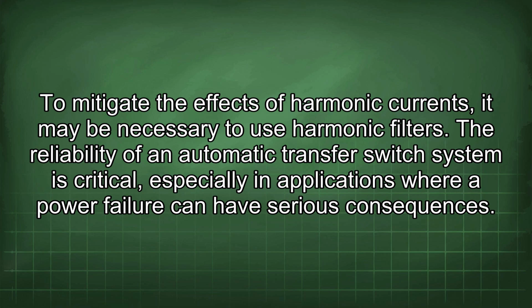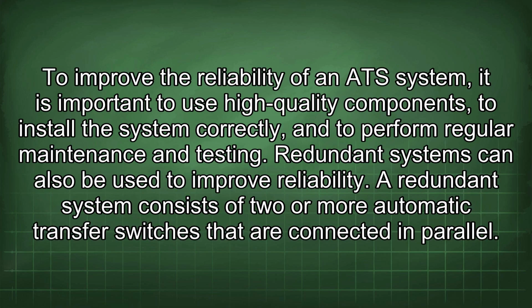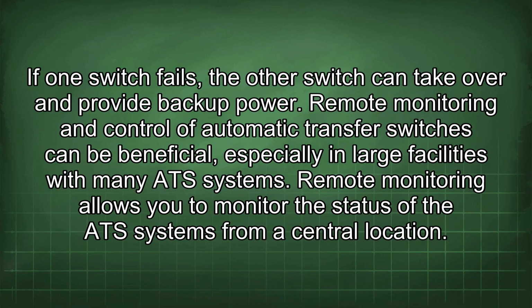The reliability of an automatic transfer switch system is critical, especially in applications where power failure can have serious consequences. To improve the reliability of an ATS system, it is important to use high-quality components, to install the system correctly, and to perform regular maintenance and testing. Redundant systems can also be used to improve reliability. A redundant system consists of two or more automatic transfer switches that are connected in parallel. If one switch fails, the other switch can take over and provide backup power.